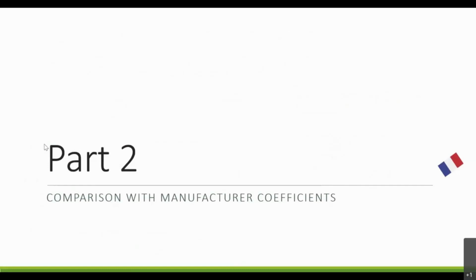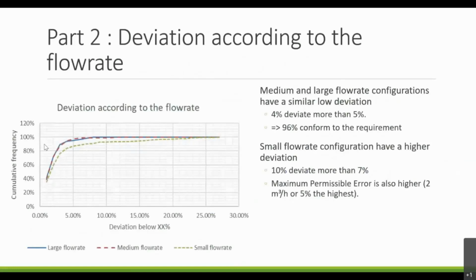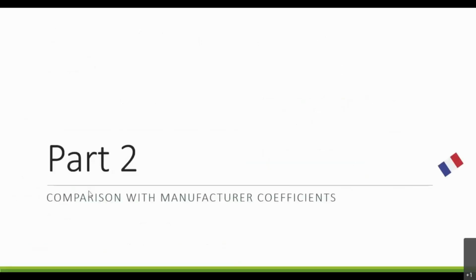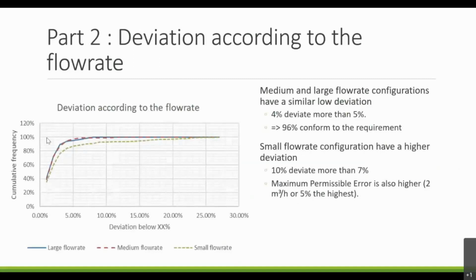Let's now move on to the second part, with the result of the comparison with manufacturer coefficients. First of all, we have found the same result regarding the deviation according to the flow rate, with medium and large flow rate configurations, which have similarly low deviations: 4% deviate by more than 5%. So that means that 96% remain conform to the requirements for medium and large flow rates, which are without ring or with open or ring A on the Blower Door fan.